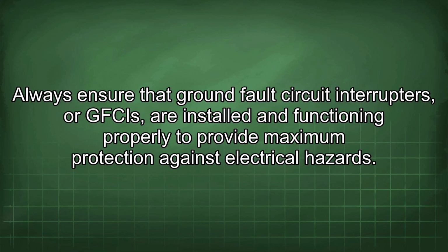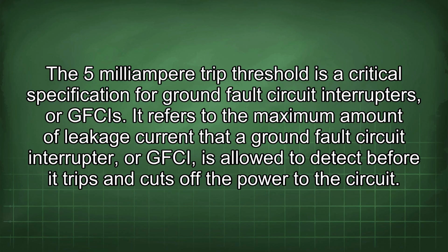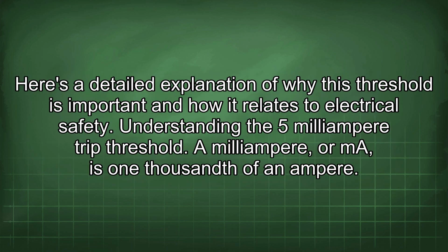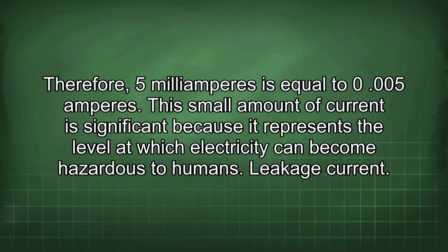electrical hazards. The 5 mA trip threshold is a critical specification for GFCIs. It refers to the maximum amount of leakage current that a GFCI is allowed to detect before it trips and cuts off the power to the circuit. Here's a detailed explanation of why this threshold is important and how it relates to electrical safety. Understanding the 5 mA trip threshold. A milliampere, or mA, is 1/1000th of an ampere. Therefore, 5 mA is equal to 0.005 amperes.